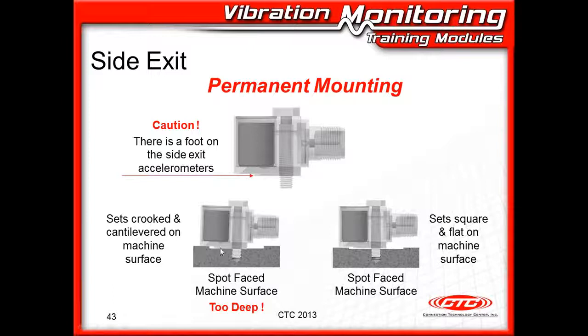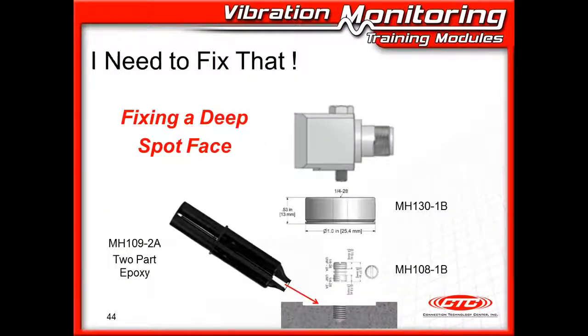That's never a good thing, not to have a surface contact. So you never want to be able to take, well, for me it would be a $1 bill, and slide in underneath this sensor anywhere. You can see here that we've got a nice spacing, and this foot is right down on the spot face where it should be. So be very careful when you're spot facing for a side exit, because if you go too deep, you're going to get into this cantilevered mode, and you're just not going to get good transmission.